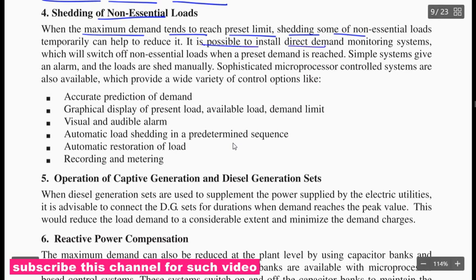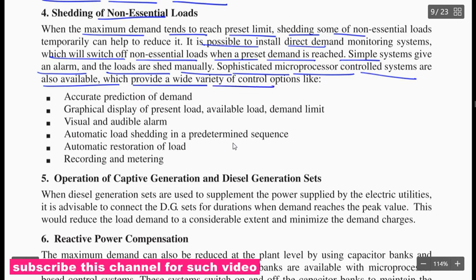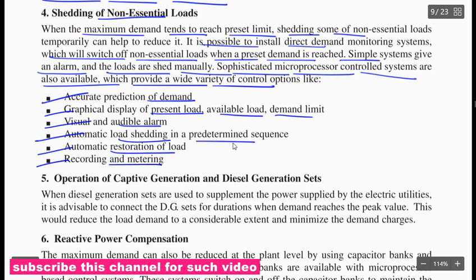It is possible to install a direct demand monitoring system which will switch off non-essential load when a preset demand is reached. A simple system gives an alarm and loads are shed manually. Sophisticated microprocessor control systems are also available which provide a wide variety of control options like accurate prediction of demand, graphical display of present load, available load and demand limit, visual and audible alarm, automatic load shedding in a predetermined sequence, automatic restoration of load, recording and metering, and operation of captive generation and diesel generator sets.